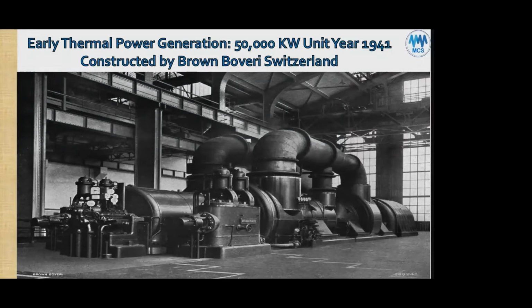So on the left-hand side, you see the high pressure turbine. And on the very left, you see the governor valves. And on the right, it looks like these are the stop valve controllers. These are on the two valves there on the right. These would be separate stop valves, either for reheat or just purely inlet. And then you have the IP with the large pipes coming off the top, IP section, and then the LP. And finally, toward the end is the generator.